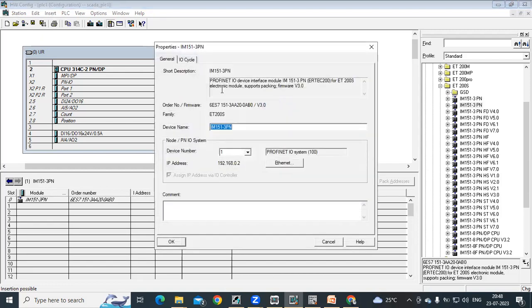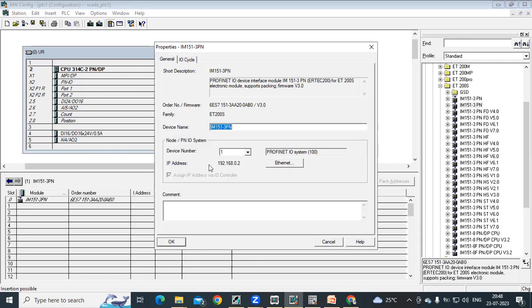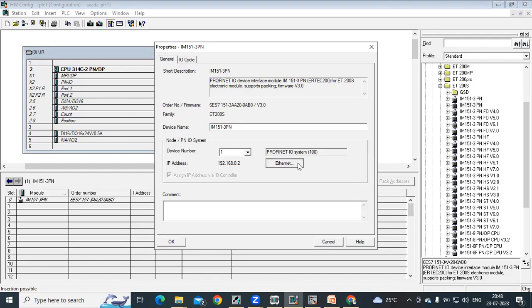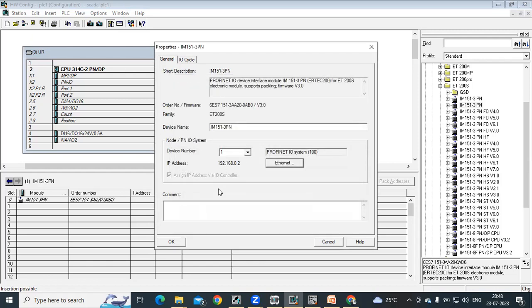Here you can see it is showing the device number as one. For this CPU it was showing zero, device number zero. Now here IP address 192.168.0.2. You can go to Ethernet here and change the IP address if required, if you want to change. Otherwise you can take the same. I'm selecting 192.168.0.2 because I am using simulator. Here on this Ethernet IM we are not having any DP switches like for Profibus. We are selecting IP address directly in software, we are feeding them, so you don't need to select DP switches here.